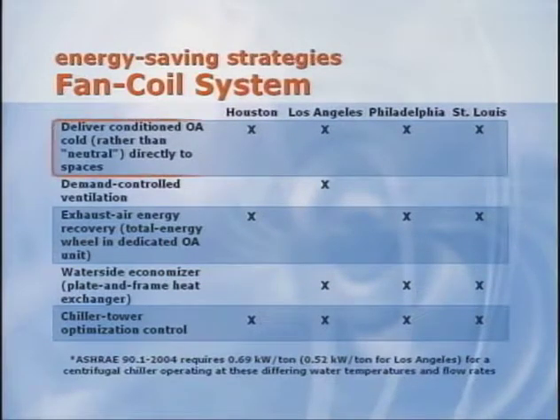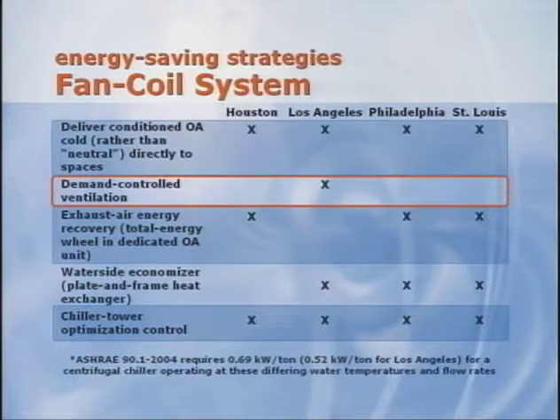The next 2 strategies relate to the dedicated outdoor air system. The conditioned outdoor air is delivered cold rather than neutral directly to the spaces. And for 3 of the locations, a total energy wheel is used to precondition the entering outdoor air. For the other location, Los Angeles, the dedicated outdoor air system had to be designed for demand control ventilation in order to reach the minimum threshold. A dedicated outdoor air system is typically designed to deliver only minimum ventilation, not full economizing airflow. So a plate and frame heat exchanger was added to the chiller plant for Los Angeles, Philadelphia, and St. Louis to provide waterside economizing. Lastly, a chiller tower optimization control sequence was used. This strategy uses the chiller plant control software to determine the optimum condenser water temperature set point that minimizes the combined energy use of the chiller and cooling tower.